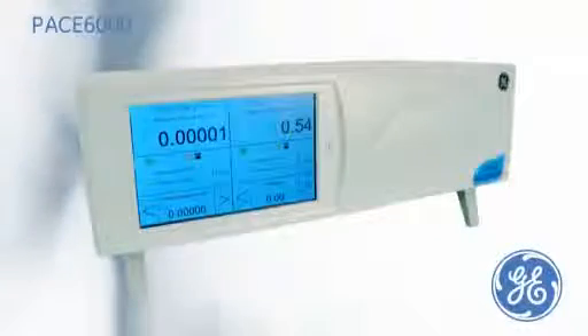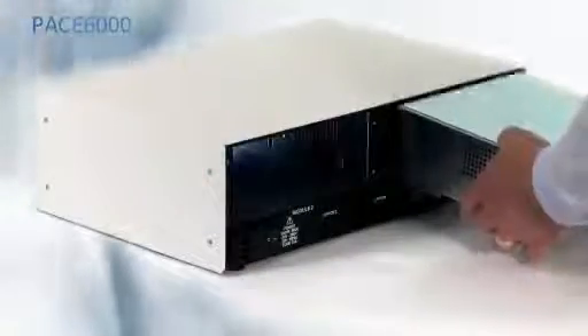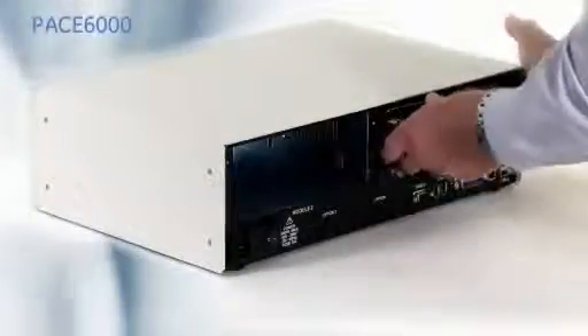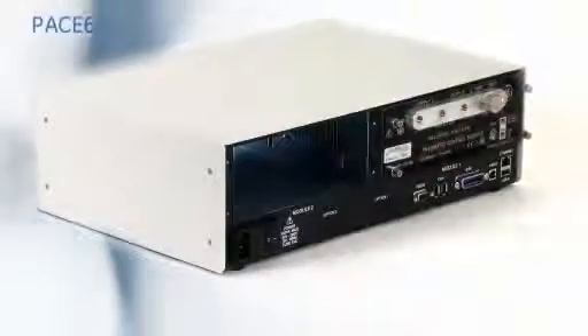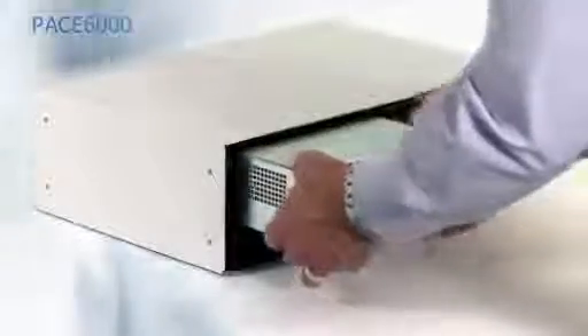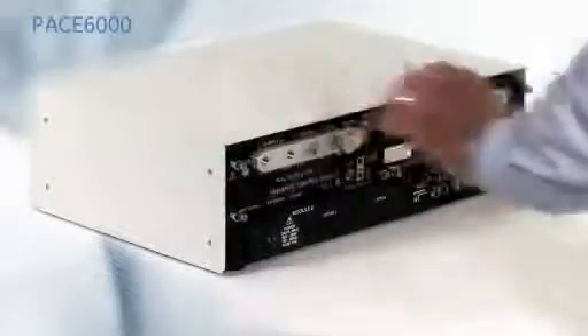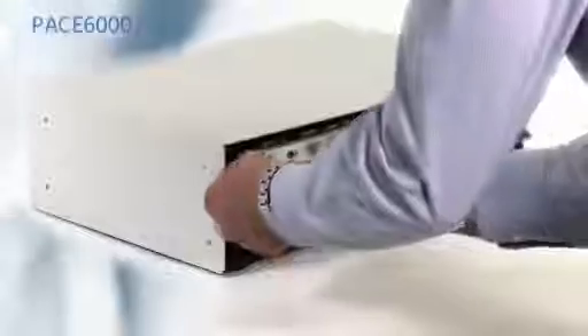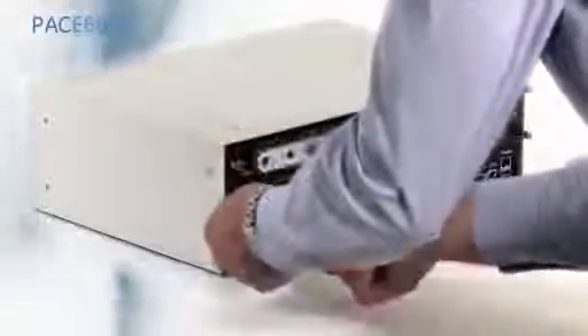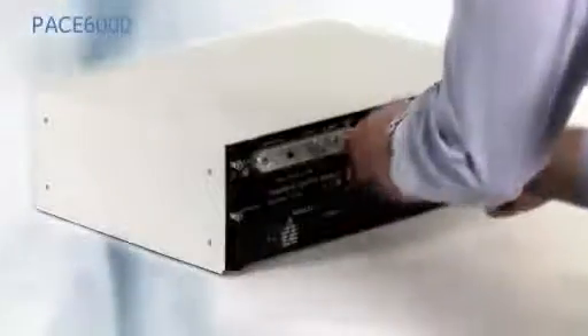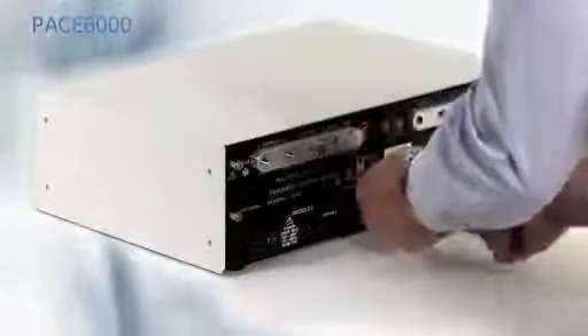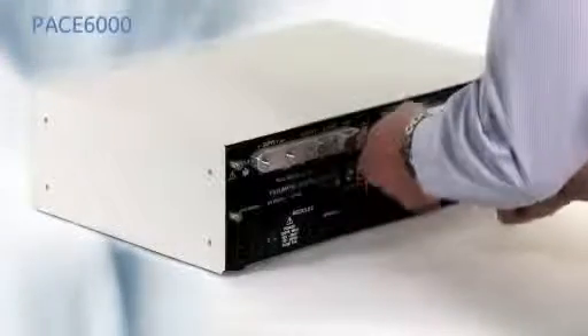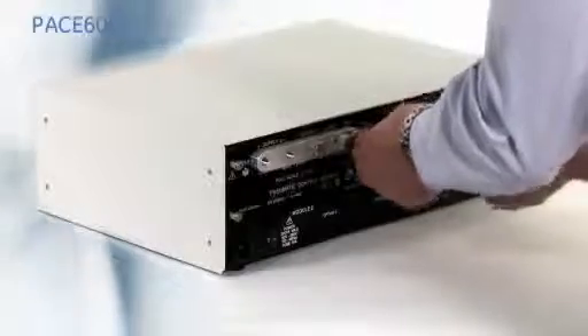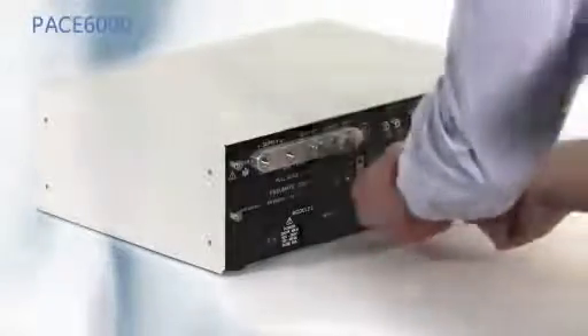This is the PACE6000 Precision Pressure Controller Calibrator, where either a single pressure control module can be fitted or two pressure modules. These modules can easily be installed and removed for recalibration or range changes, enabling future expansion as business needs change. The measurement precision of the modules is 0.005% of reading plus 0.05% of full scale with a control stability of 10 ppm.